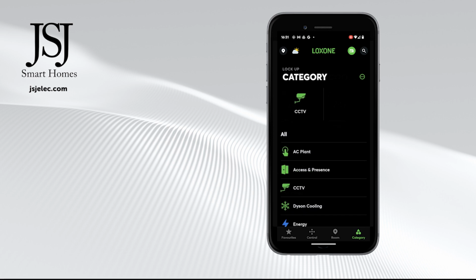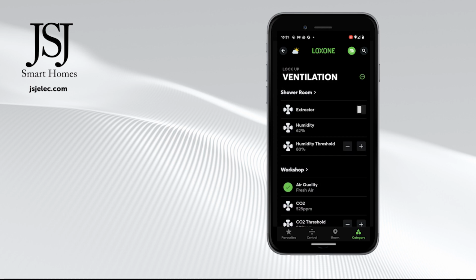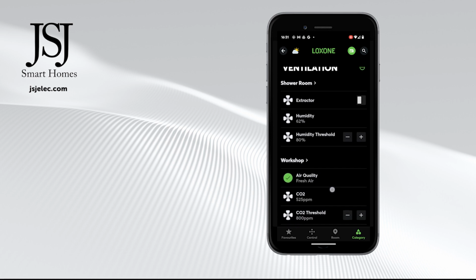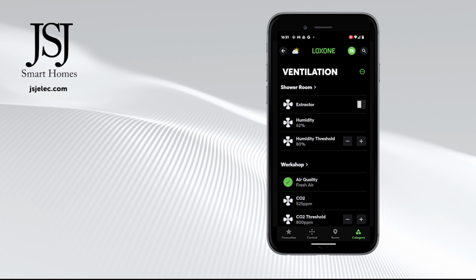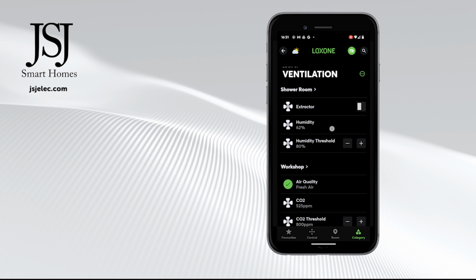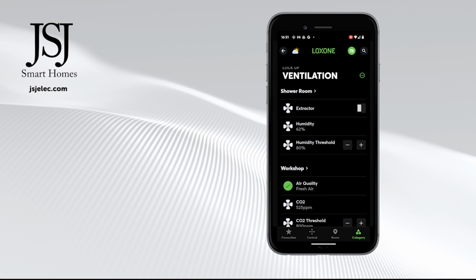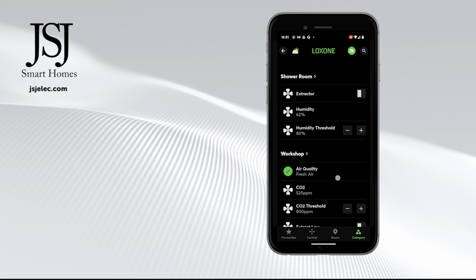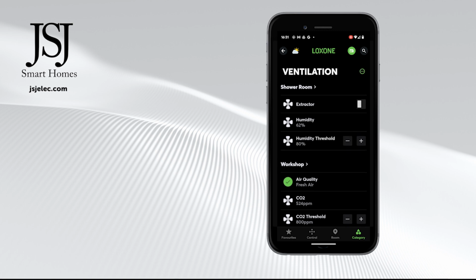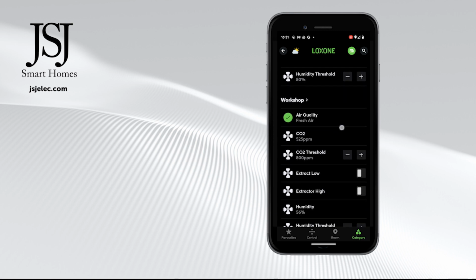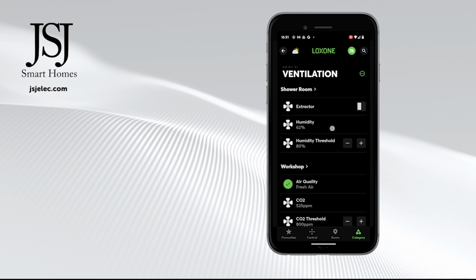And then I'll just go through back to the categories. We've got ventilation as a separate category here. In this particular instance, we do have a humidity sensor, so we don't just kick the ventilation in on the basis of heat, we can also do it on the basis of humidity. We can adjust where the threshold point is. So at the moment it's measuring 62%. If I were to pull the threshold down, then the extractor would kick in automatically.